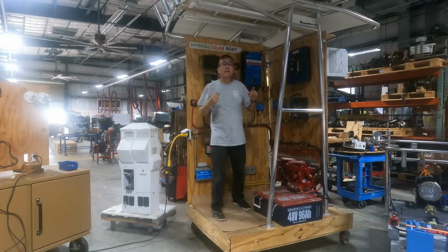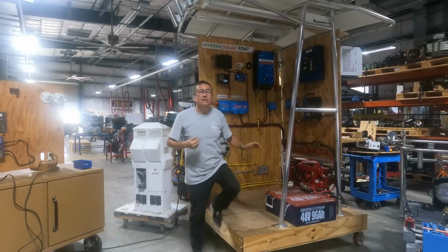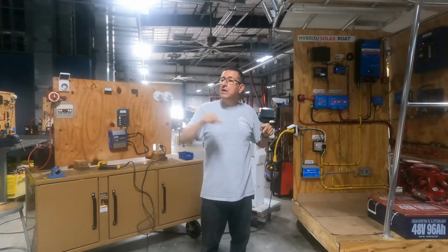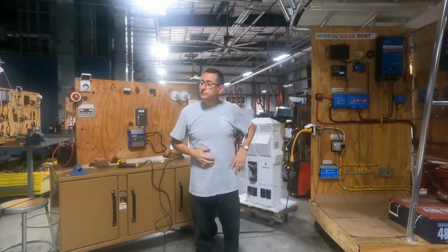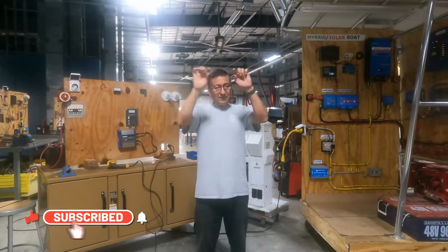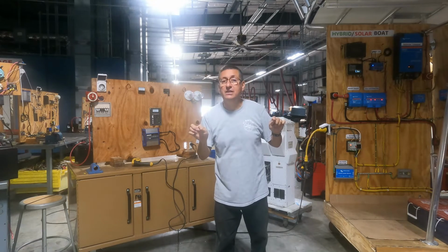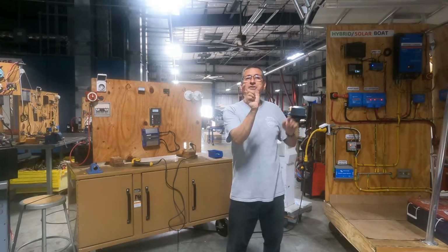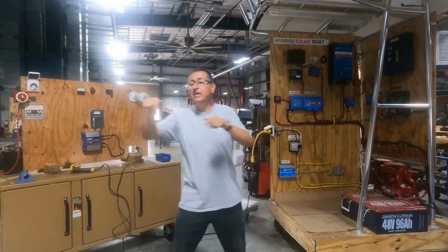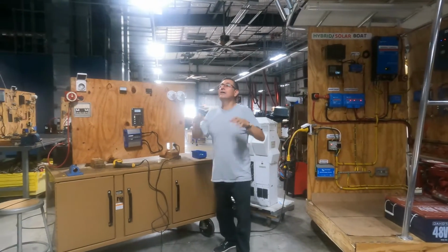You remember the previous one, the traditional inverter? The traditional inverter converts DC power into AC and sends that power to the AC panel. Mr. Lopez, but the old inverters, they say inverter/charger. Yes, because that inverter internally has a small charger. And that small charger, when the inverter is not inverting, is not producing power, receives power from one breaker in the AC panel. You remember? It activates the charger to keep the battery bank charged.